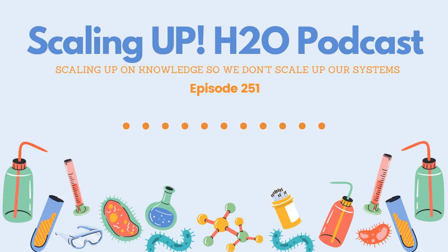First thing I want to do is clean that, and then I might put that into a standard solution. Or if I know what the sample is, and I know the conductivity or whatever I'm trying to test, and I've got a good reading on that, I can use that solution. It depends if you do a 1, 2, or 3-point calibration. Talk to your control manufacturers to learn more about that. We'll probably do a show someday about what the differences are. Today, just know that you want to keep things clean. You want to be able to trust them, and the way you trust them is to make sure that they are calibrated. If you need to calibrate something, follow the method that makes the most sense for you.